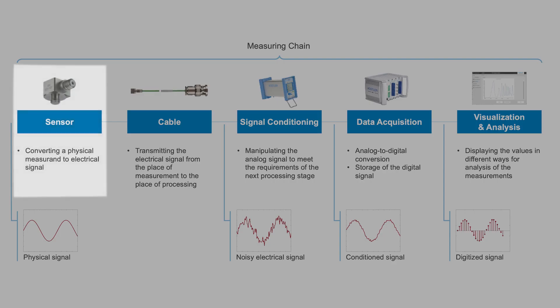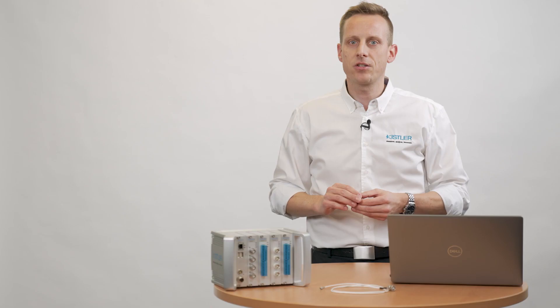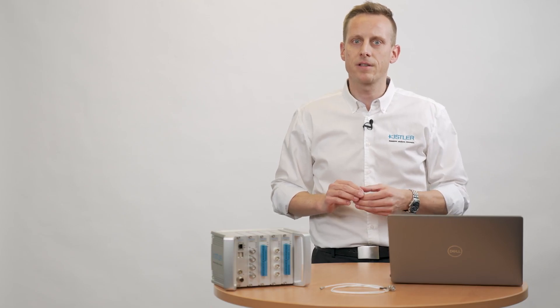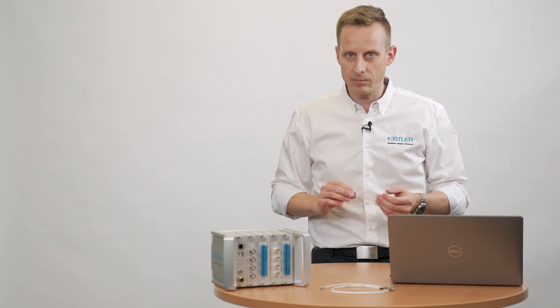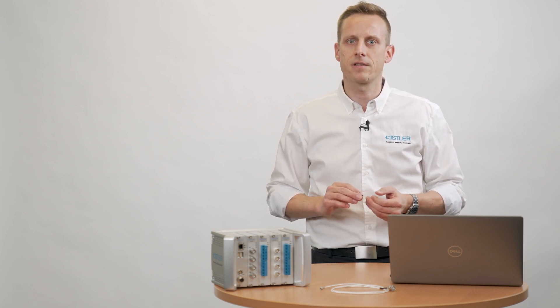Let's start with an overview of the full measuring chain. The sensor converts the physical signal into an electrical signal — for example a force, pressure, or like this one, acceleration. The cable looks like a no-brainer and is often underestimated, but depending on the application it may have a crucial influence on the measurement. Good cabling helps a lot to reduce noise and interfering signals.